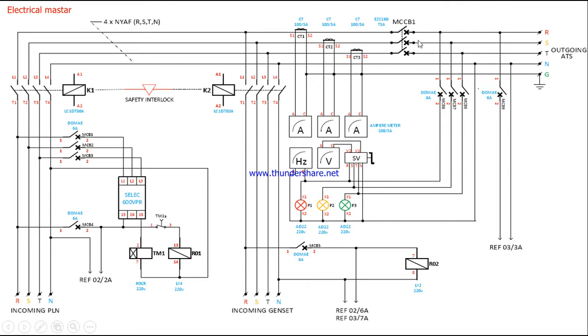When the load breaker is manually closed, it connects to the outgoing loads. Similarly, the DG supply is connected to the K2 magnetic contactor. Whenever K2 is energized, the supply goes to MCCB1, and from MCCB1, when manually closed, it goes to the load. Here we are making an interlock between the electricity contactor and the generator contactor — only one contactor can be active at a time, either the DG contactor or the main contactor.